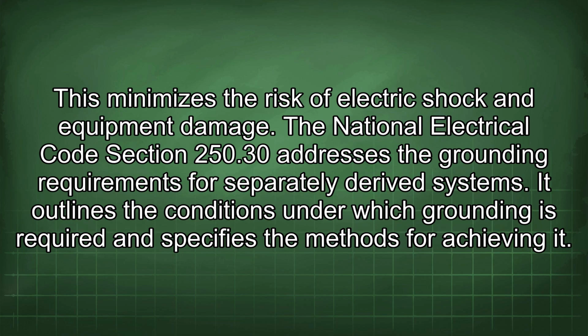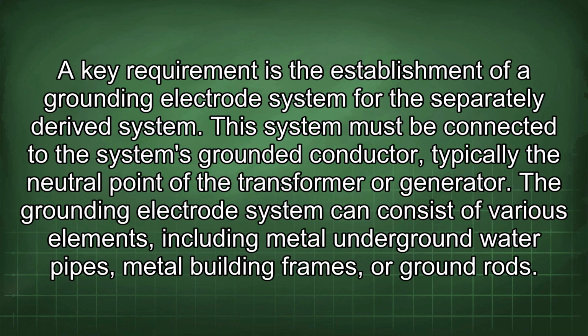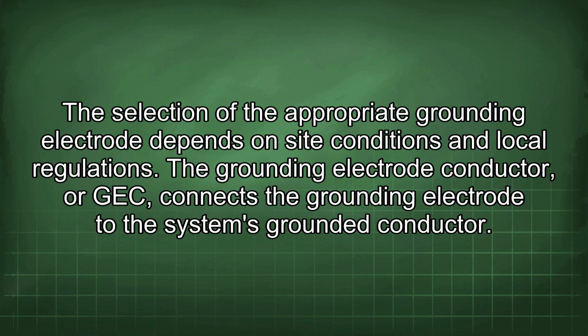The National Electrical Code Section 250.30 addresses the grounding requirements for separately derived systems. It outlines the conditions under which grounding is required and specifies the methods for achieving it. A key requirement is the establishment of a grounding electrode system for the separately derived system. This system must be connected to the system's grounded conductor, typically the neutral point of the transformer or generator. The grounding electrode system can consist of various elements, including metal underground water pipes, metal building frames, or ground rods. The selection of the appropriate grounding electrode depends on site conditions and local regulations.